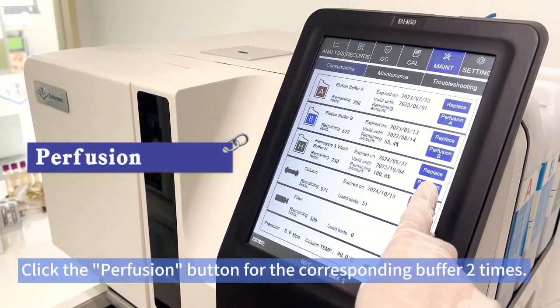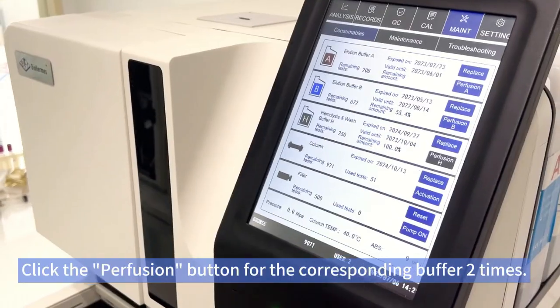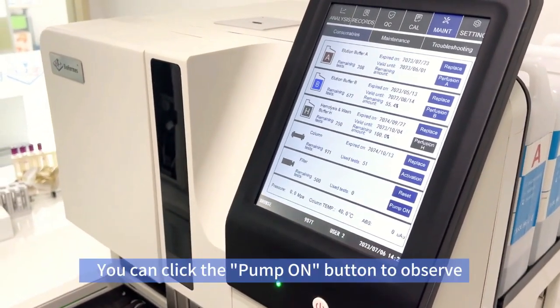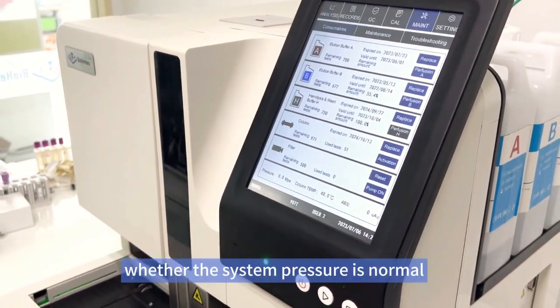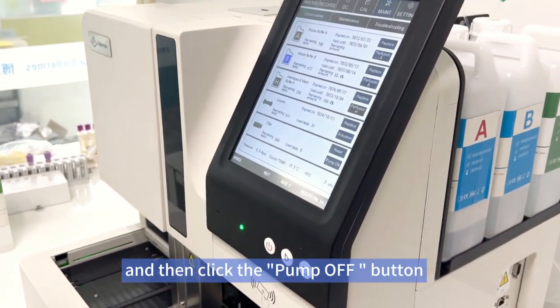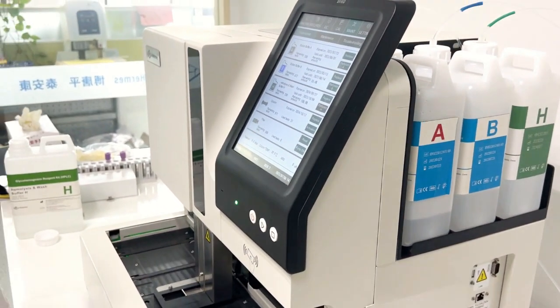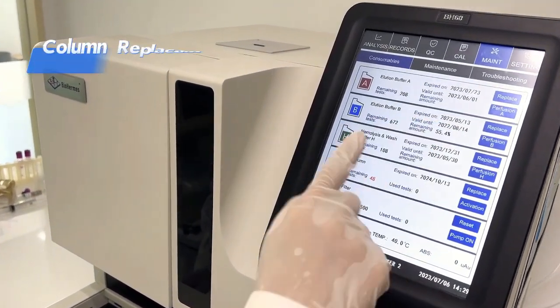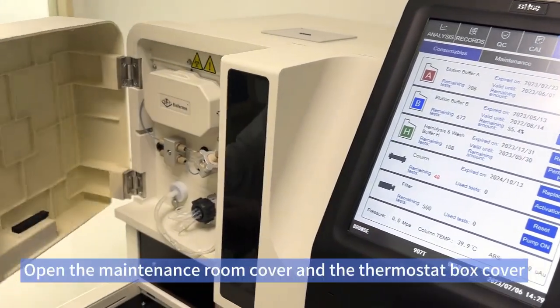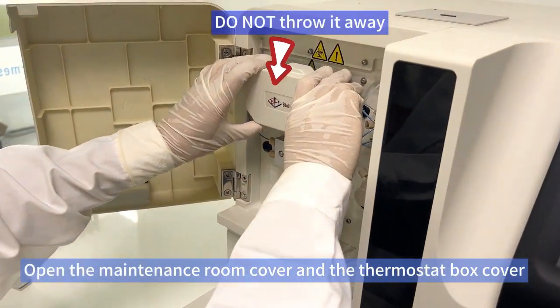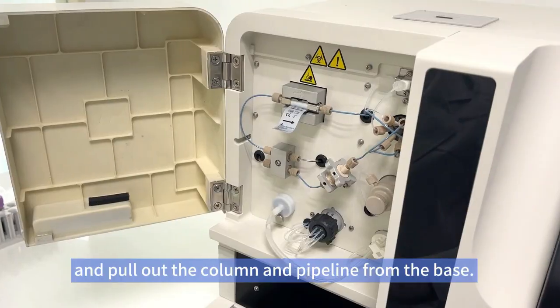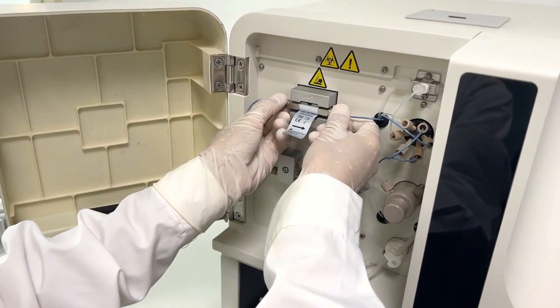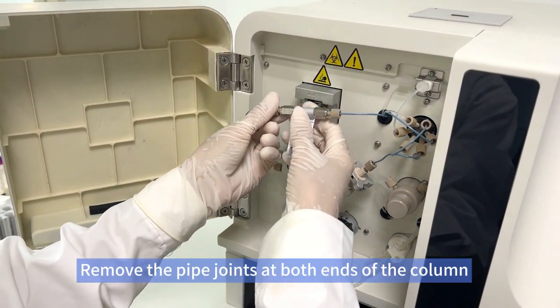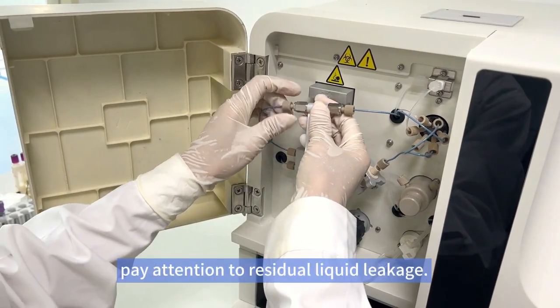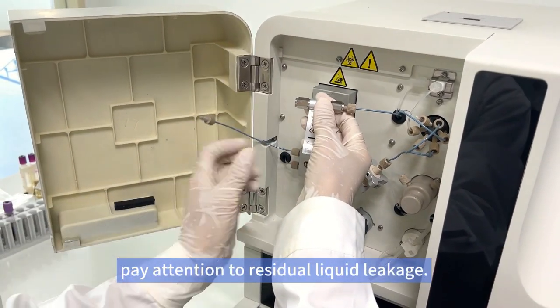Perfusion. Click the Perfusion button for the corresponding buffer 2 times. You can click the Pump On button to observe whether the system pressure is normal, and then click the Pump Off button. Column replacement and degassing. Column replacement. Open the maintenance room cover and the thermostat box cover, and pull out the column and pipeline from the base. Remove the pipe joints at both ends of the column. Pay attention to residual liquid leakage.